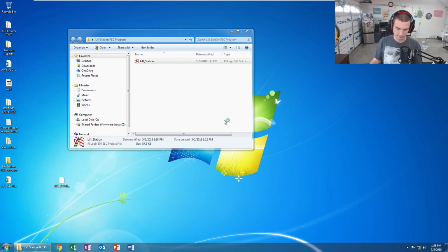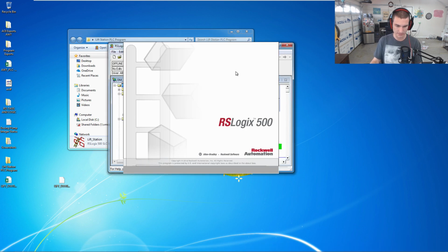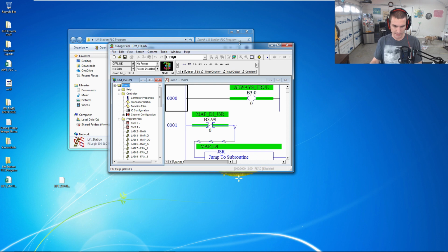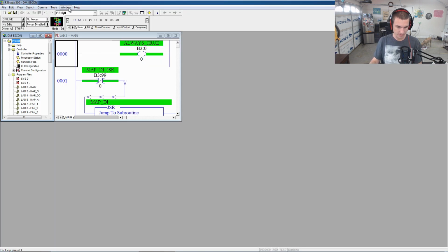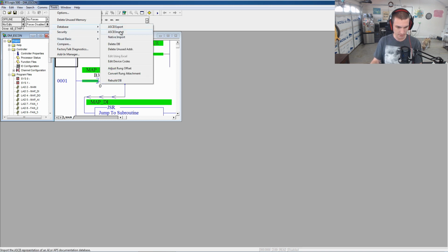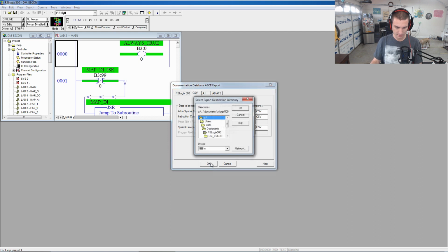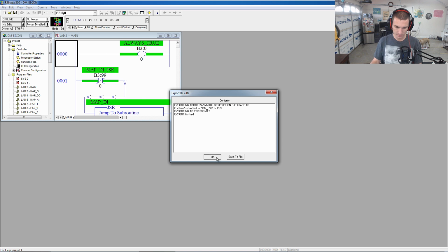DM_ESCON. I know exactly what I did wrong. I'll share it with you guys in a second. So we had fan 1 and fan 2 and fan 3. But we also had pump 1 and pump 2. So pump 1 and pump 2 collided with other addresses. So I'm just going to go here. I'm going to do an ASCII export, CSV, DM_ESCON, okay, to the desktop. Okay, with me so far.